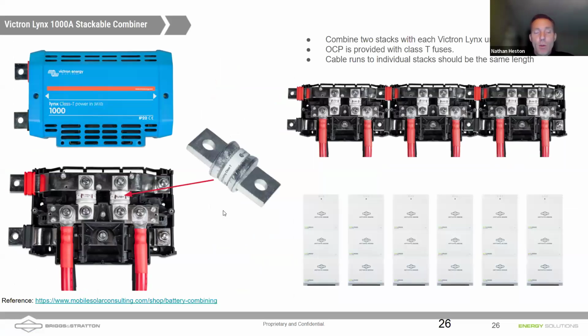And let me show you a great example of a very low cost combiner. So these Victron 1000 amp DC combiners, and make sure you do get the one with the M10 lugs. So that's M10, the size of the studs that are here. You can then provide individual overcurrent protection on each of your inputs. And these are stackable. I think on the link here on the screen, these things are about $160 each. And the fuses, typically you buy a pack of those fuses for about $35 each. This is a very low cost way to do a combiner.